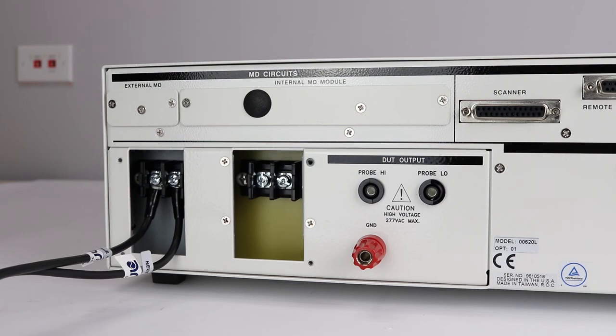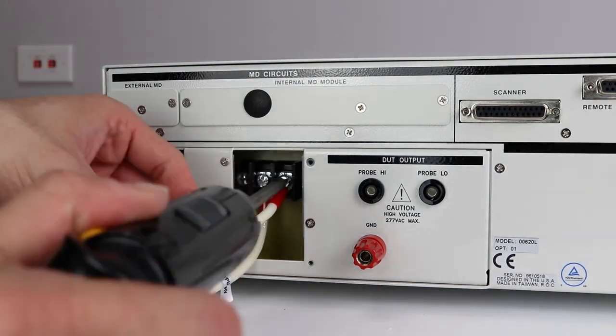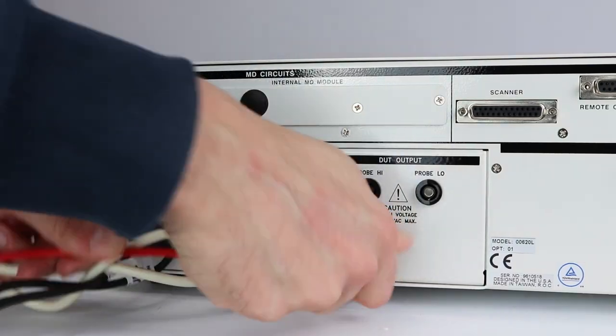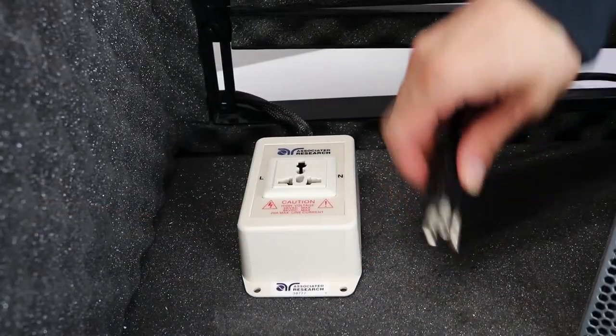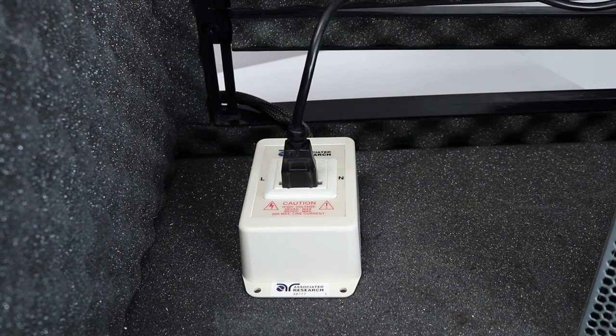Next, we're going to connect to the adapter box. These connections provide power to the DUT during a line leakage test. Connect the adapter box to the line, neutral, and ground terminals on the rear panel of the LineCHEK. To connect the DUT to the LineCHEK, simply plug in the class 1 DUT into the adapter box.